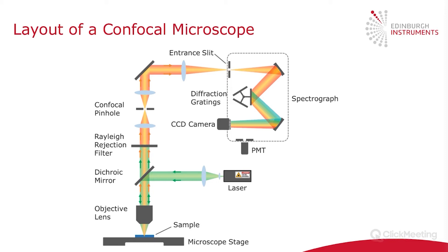The spectrograph is used to wavelength-select the signal. The light comes in and is focused using a mirror onto a diffraction grating, which separates the light into its constituent wavelengths. This is usually a grating turret — I've shown three here, but on our Raman microscopes there are actually five grating turrets.